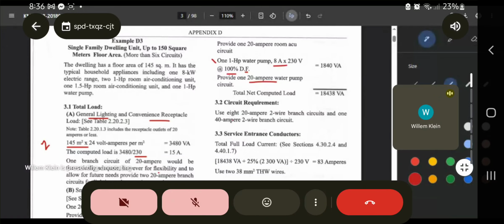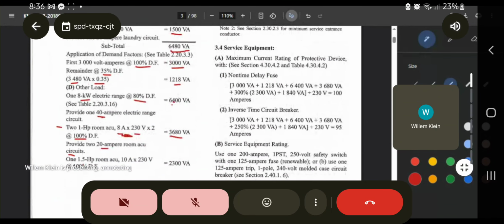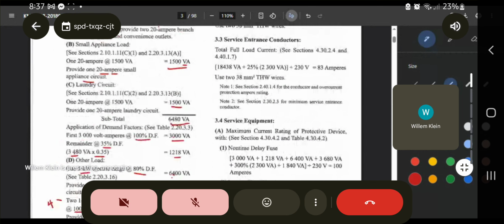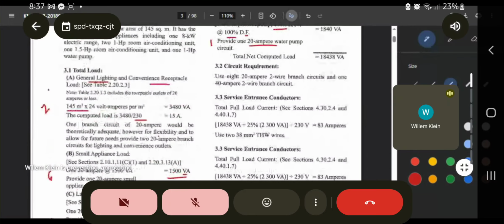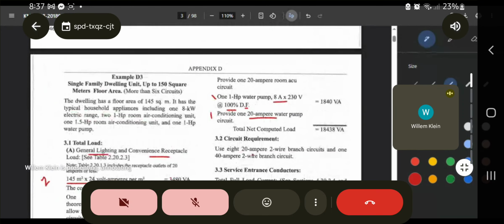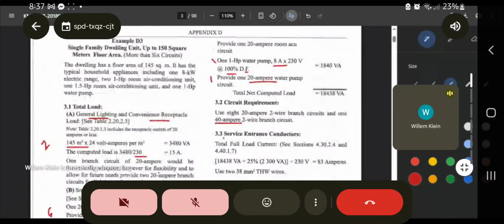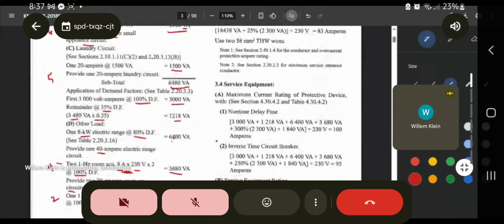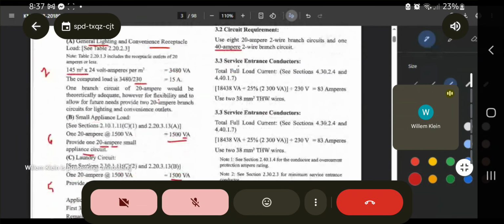Okay. So circuit requirements. So this is the total branch circuit. So use 8 20 ampere two wire branch circuits. No, so how come we have 8? So 'di ba you have this one, 1, 2, okay, and then 3 and 4, and then 5, 6, and then 7, 8. No, if you separated the lighting and the convenience. Okay? So that's why you have 8 20 ampere circuits. And then you have one 40 ampere circuit for your cooking range or your electric range. Okay? And then your service entrance conductors.